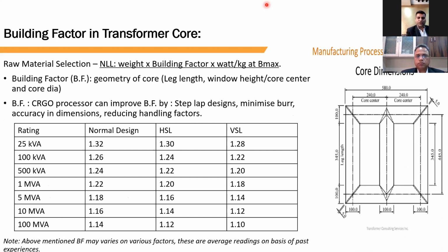So here we are going to discuss building factor in more detail. For raw material selection of CRGO for any transformer core, we need to know the no load loss performance, and for that we need to understand how it is calculated. As I told you in the previous slide, the formula of no load loss is the weight of the CRGO core, building factor, and watt loss at design flux density. Bmax is a short form of design flux density. Building factor depends on many parameters. One by one, we are going to discuss them in detail in the next slide.